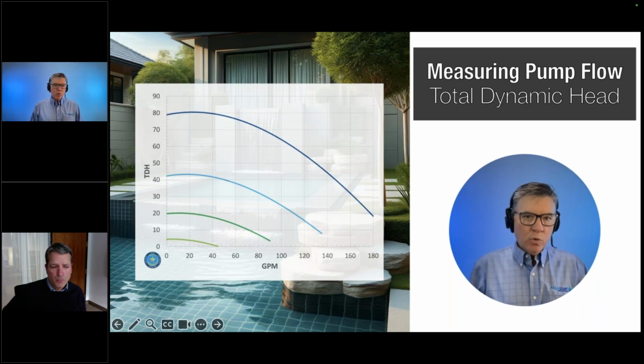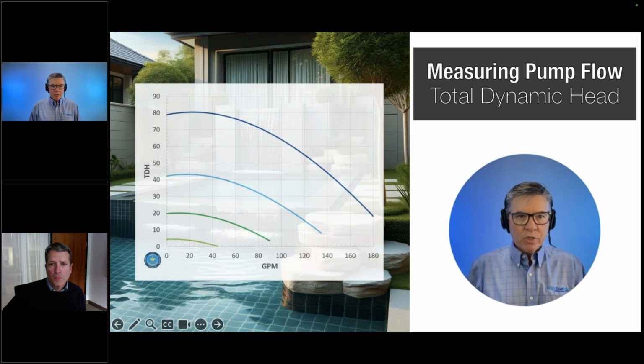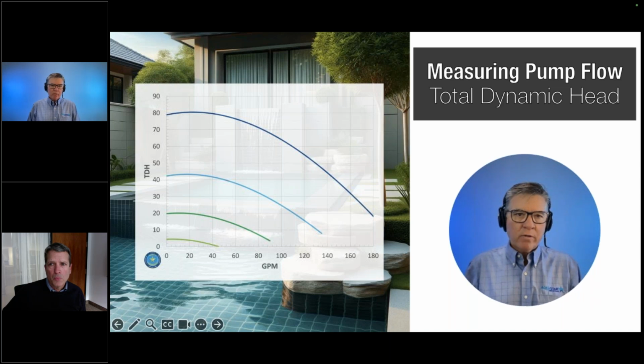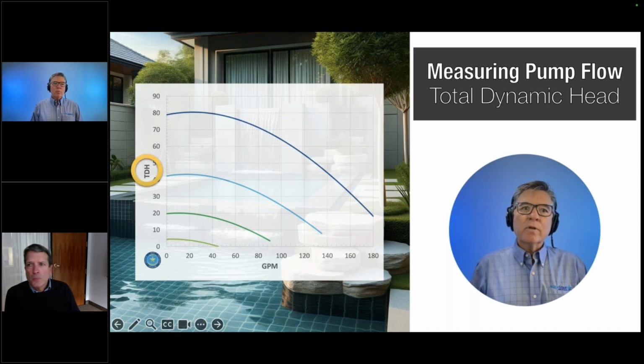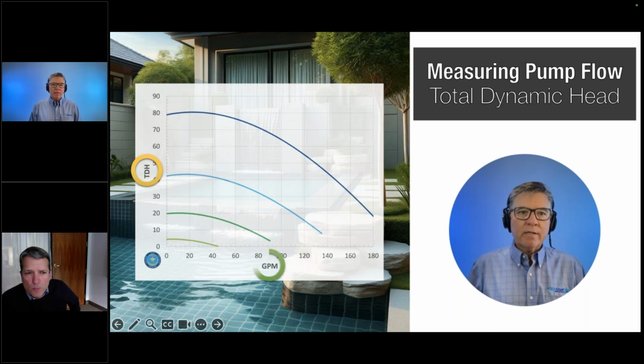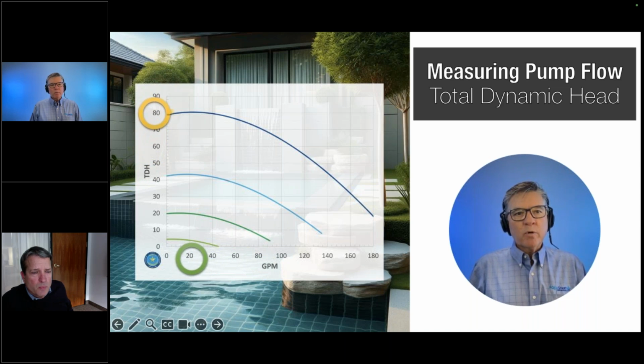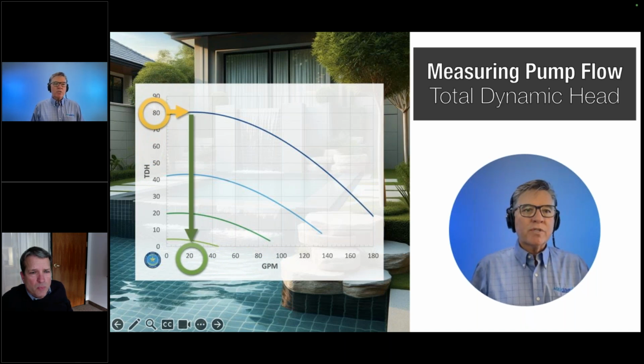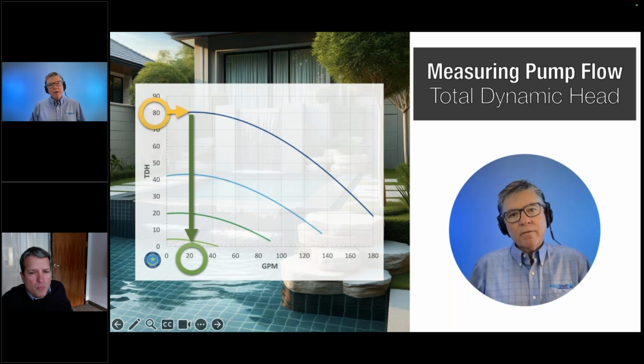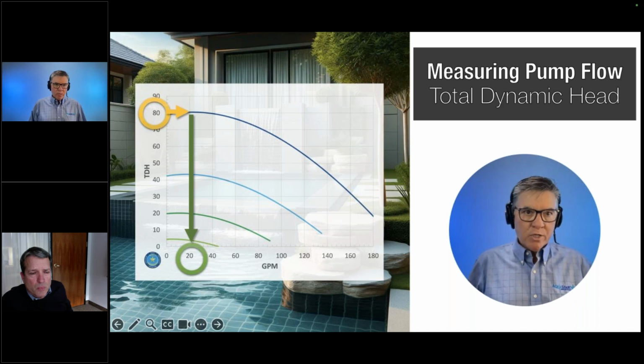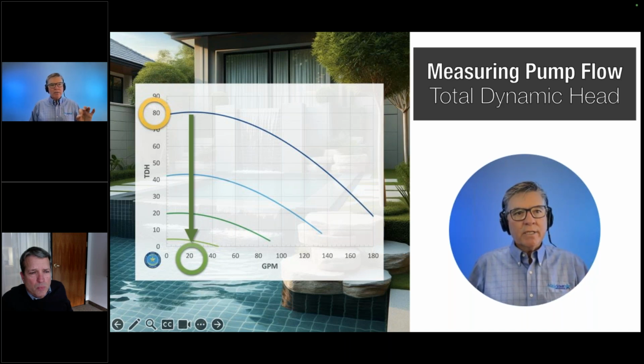These are things you need to know as a pool professional to really achieve the goal of maintaining amazing pools with water features and all of that. So let's start with, you need to understand what total dynamic head is. That's what's on the left side of swimming pool performance curves, and it's what is used to size pipes based on hydraulic calculations on new pool design. Basically, the higher the head or the higher the pressure, which could be higher filter pressure or higher vacuum pressure, those all drive higher TDH.